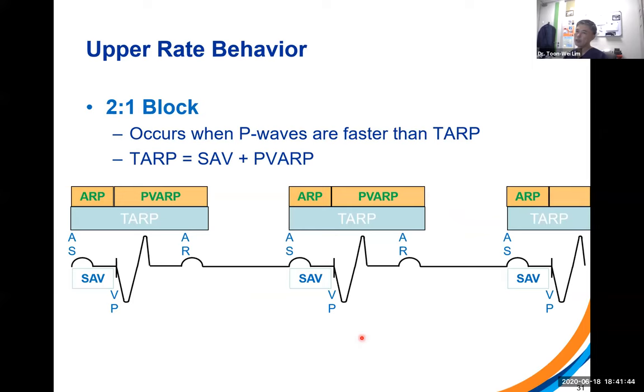If, however, your A-sense events are even faster and actually shorter than what we call the TARP, or the total atrial refractory period, which is the sum of the sense AV interval with the post-ventricular atrial refractory period, called the PVARP, then every other atrial event will fall within your PVARP. And when that happens, you'll get 2-to-1 behavior instead.